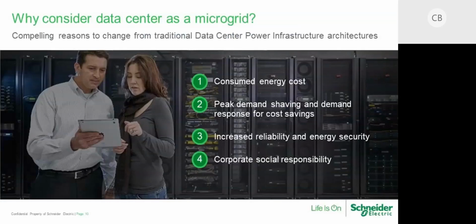So when we look at why data centers should consider a microgrid, I think there are a few compelling reasons. First and foremost, it's the consumed energy cost. We all understand that buying electricity from the utility company will just continue to go up. So electricity from the utility is becoming more and more expensive, and at the same time, on-site generation is becoming less expensive. So we're creating this difference, and therefore having a predictable energy cost will help us. And then when we look at our utility bill, and it varies by operation, typically 50% of the utility bill is the actual energy, the kilowatt hours we have consumed. And the other 50% are these peaks. So this is kilowatts needed at a certain period of time.